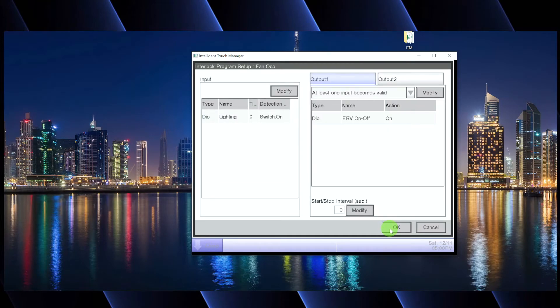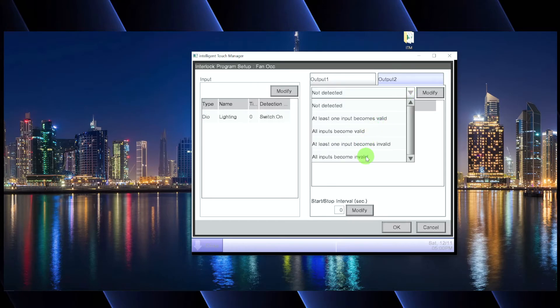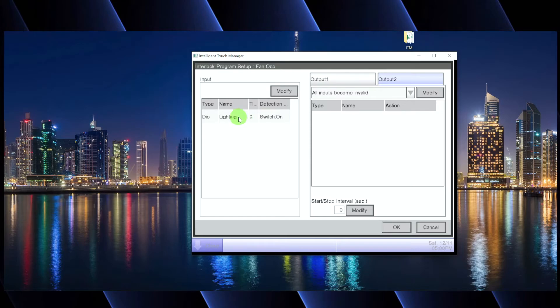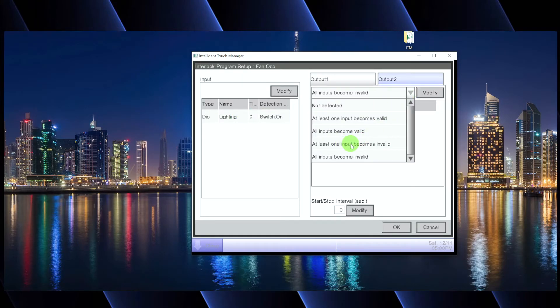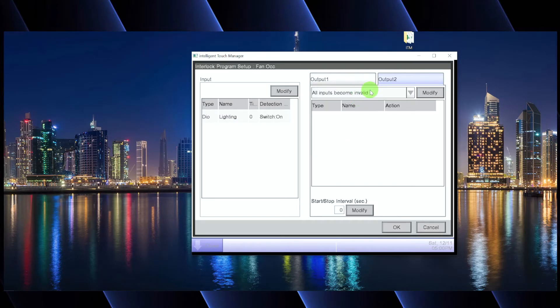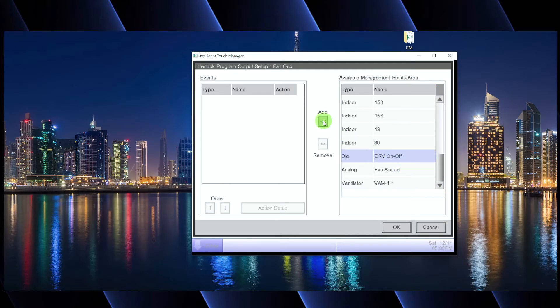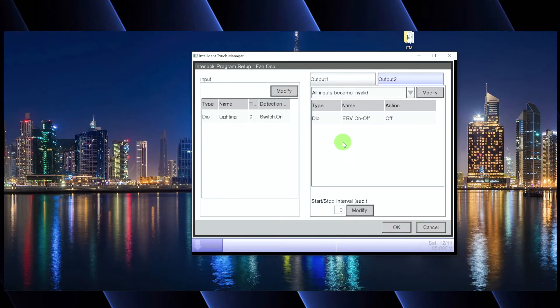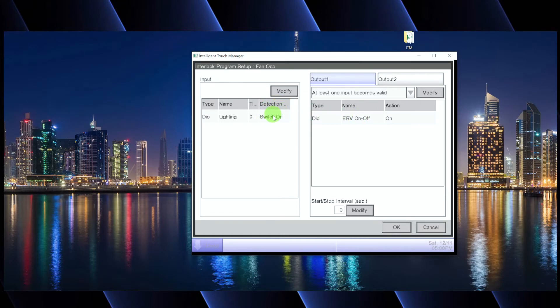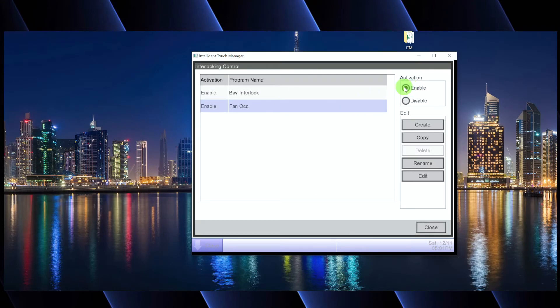Maybe it's the lighting in the bathroom and the ERV is exhausting air from the bathroom. Anytime the light is on, someone's in there and we want to exhaust that air. So if the lights turn on, we simply turn on the ERV. Output two would be: if all inputs become invalid — the lights turn off — then the ERV turns off. We go to Modify, go down to the ERV, move it over, turn it off, hit OK, and now we have a basic interlock. Hopefully the lights are on an occupancy sensor with a delay so it doesn't turn off the ERV the moment they leave. We hit OK and Enable that interlock.